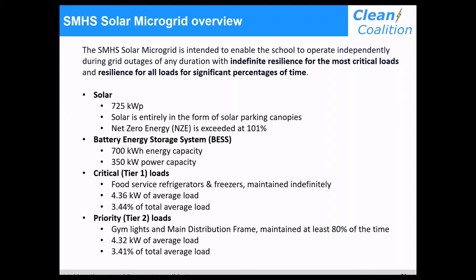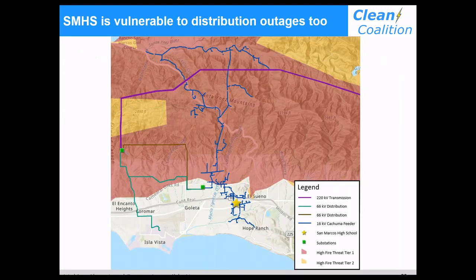The lights and plug loads there, and also what Santa Barbara Unified School District calls the main distribution frame, which is the communication system, make up the emergency staging area and communication systems as tier 2 loads. These are almost identical in average load size to the tier 1s, and need to be maintained 80% plus of the time.